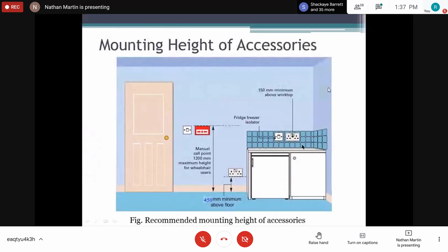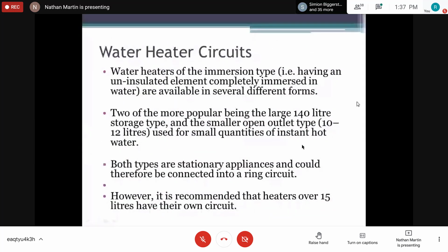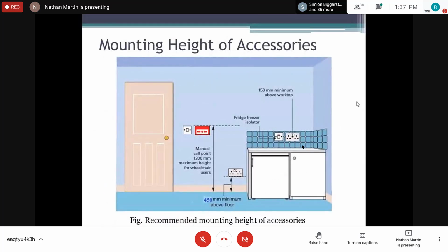All right, the mounting height of all of this that we talk about. We talk about all this connection of power circuits and lighting circuits, but how do we mount them and how do we determine that these are actually mounted in the right positions? For the maximum height of your switches, we're talking about 4 feet 6 inches or 1200 millimeters. The minimum height of your outlets above floor is 18 inches or 450 millimeters. These should work out to the millimeter. Above your surfaces, to the top of the outlet should be 150 millimeters above the worktop, which you can work out.